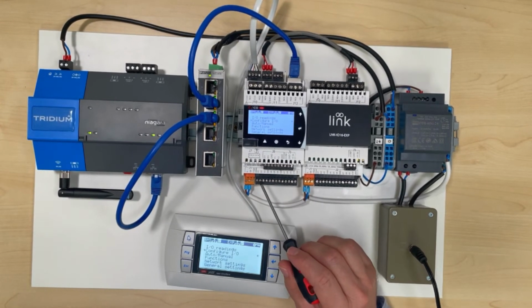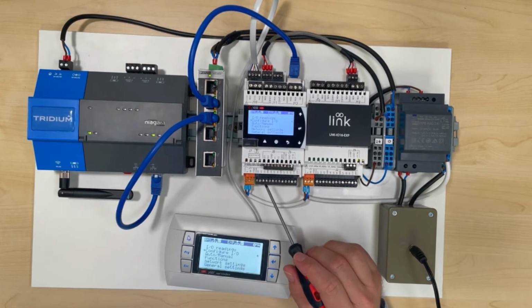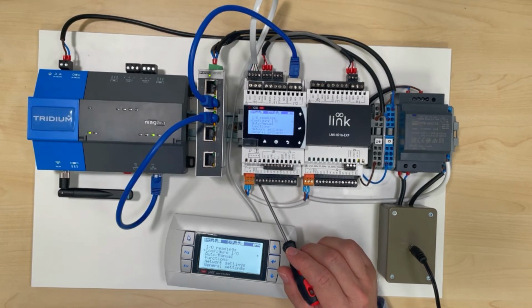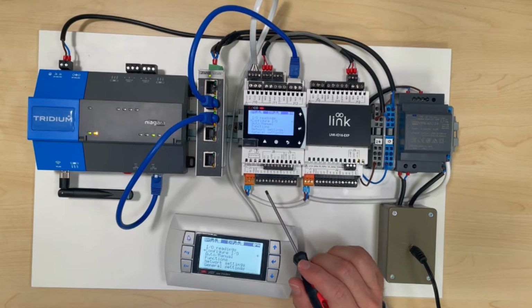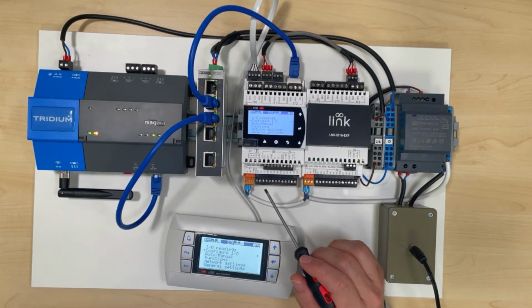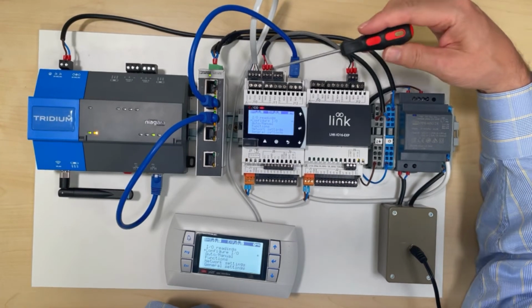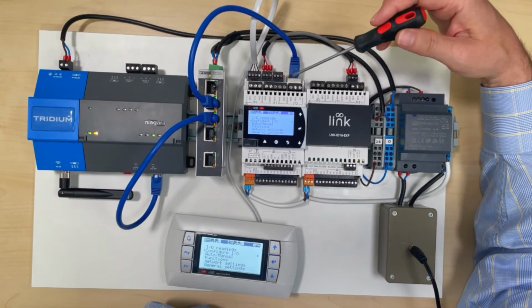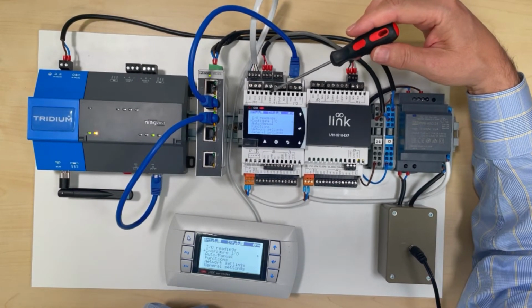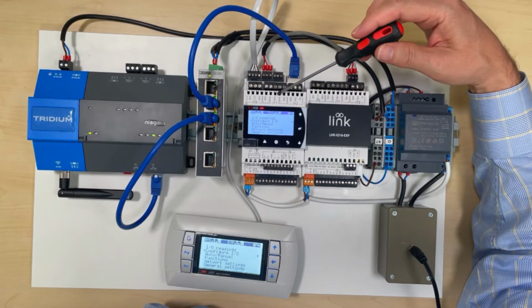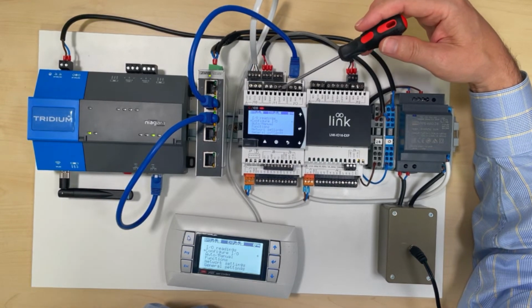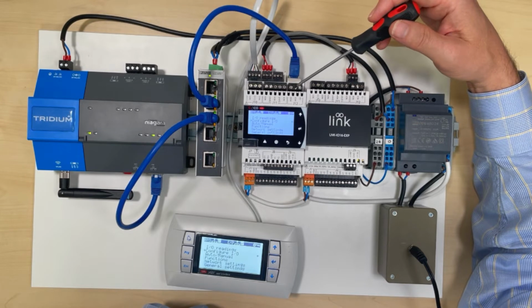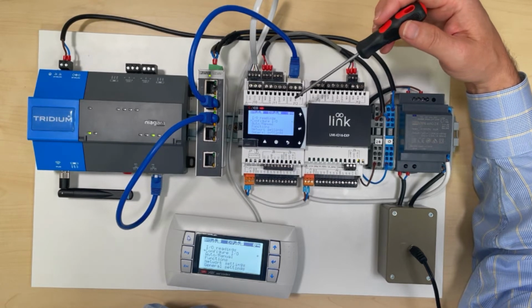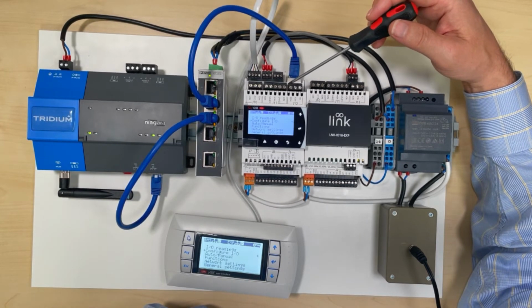So these universals can be used as outputs as well, and they can be used as 0 to 10 volt, or they can be used as pulse width modulation at 100 hertz or 2 kilohertz. Moving up to the top here, we've got a set of relay or digital outputs. The first 5 have just got a common and normally open contact, and they can handle up to 5 amps.